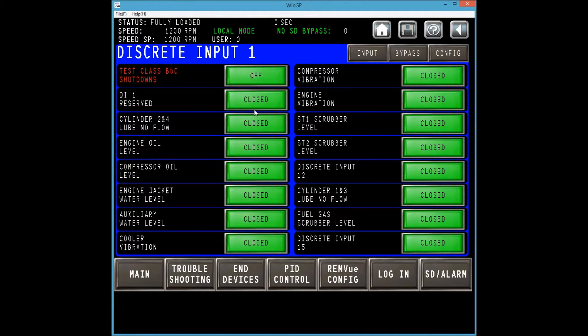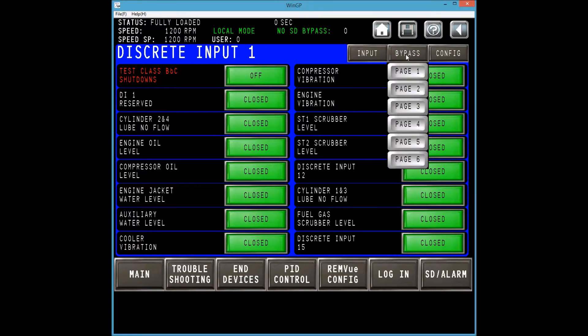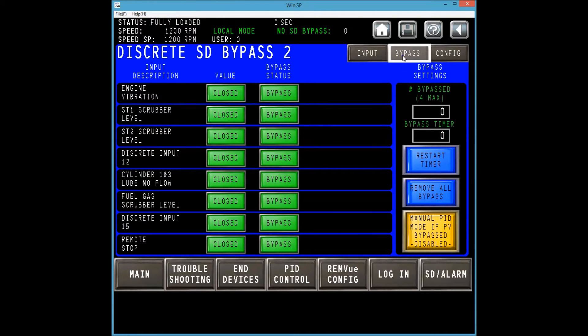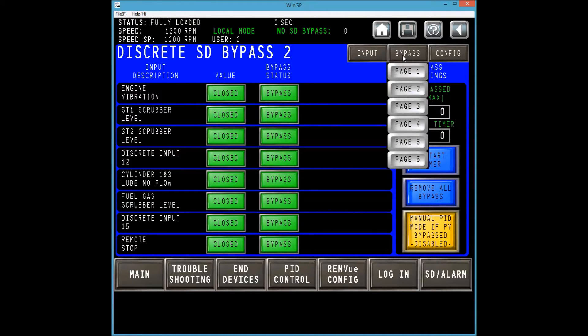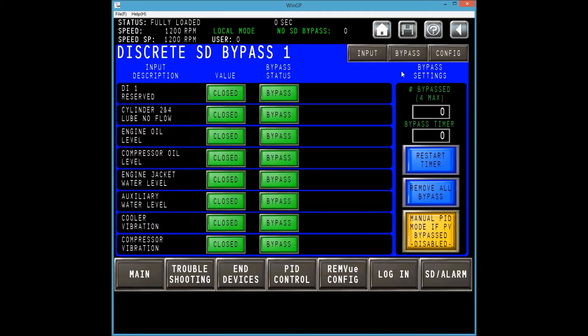After selecting our I.O. channel type, we are shown a list of the specific I.O. channels. From here, we need to navigate to the bypass screen. Select bypass at the top of the screen. Leaf through the pages in the drop-down menu until you locate your desired I.O. channel. In this video, we will search for engine oil level, which happens to be on page 1 of the bypass drop-down menu. To place our I.O. channel in bypass state, we press the green bypass button.